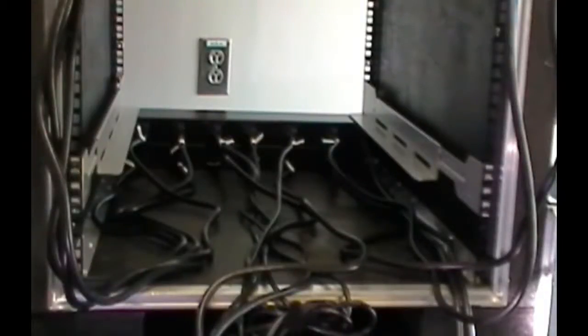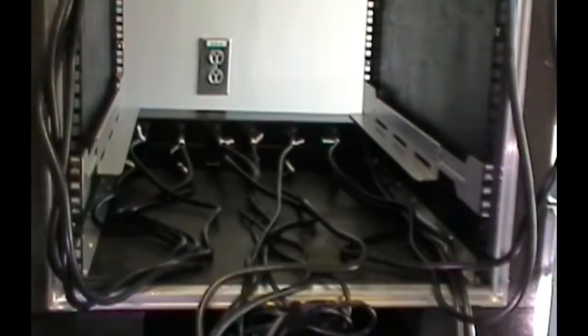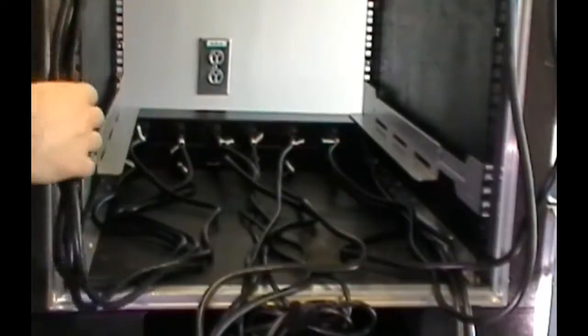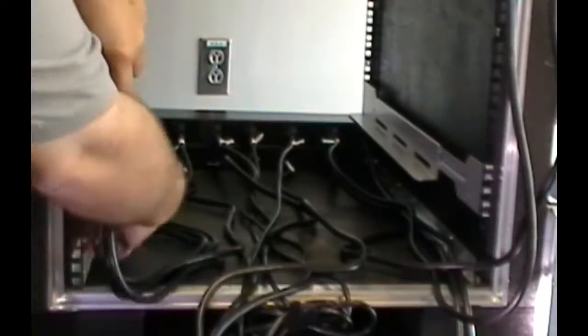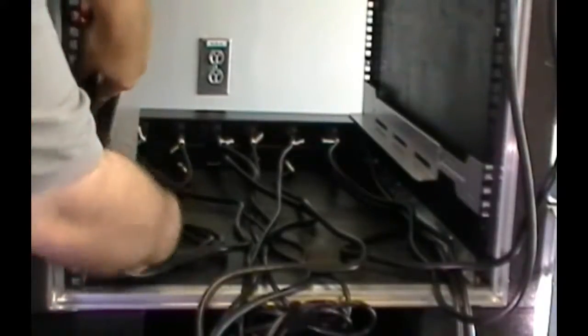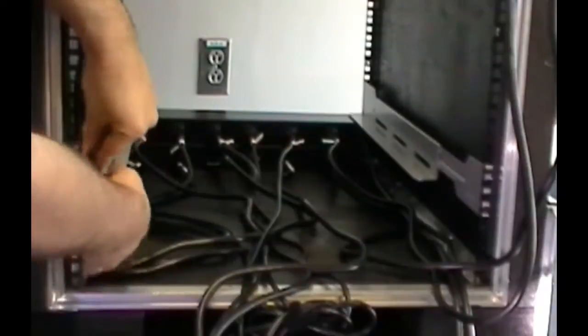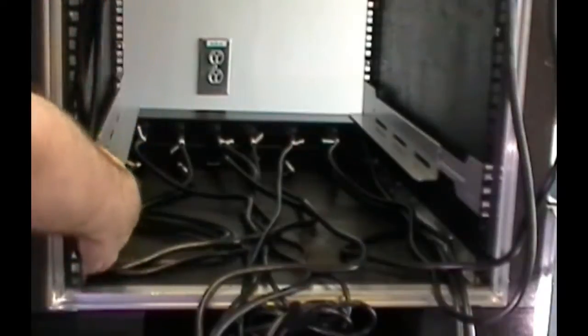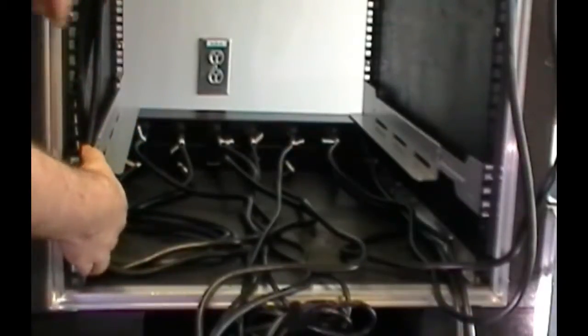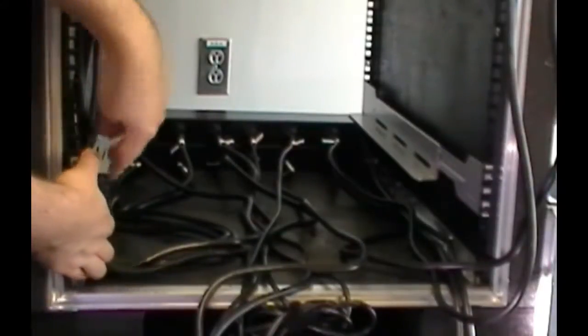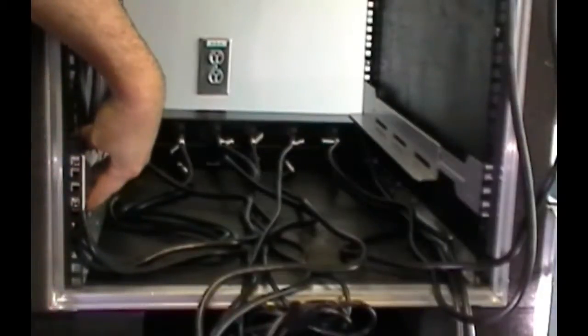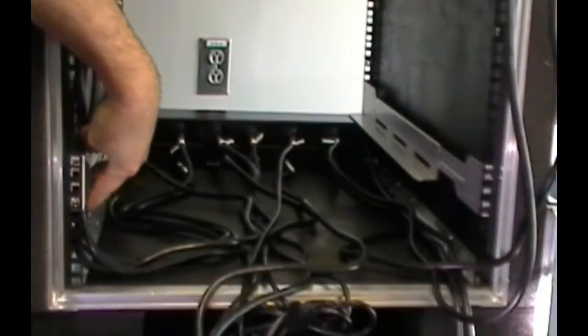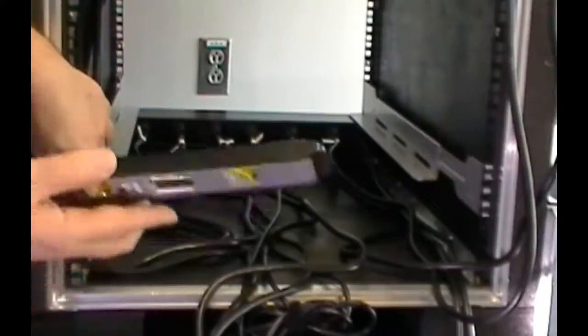At the rear of the cabinet, due to the orientation of the power distribution units, we had to plug in and label our power cables first. Because they will be hard to get to after we install the components. And before we fasten the rails, we take the opportunity to do some cable management and place the power cables behind the rail kits.